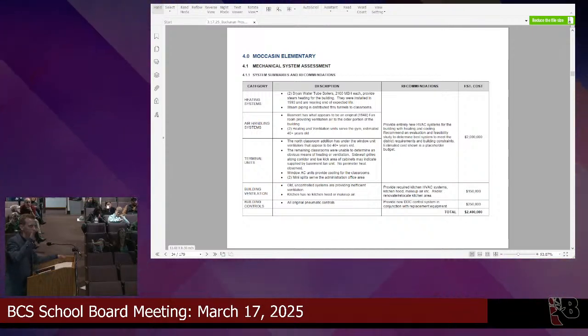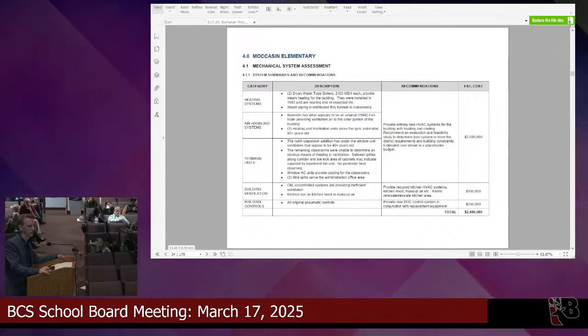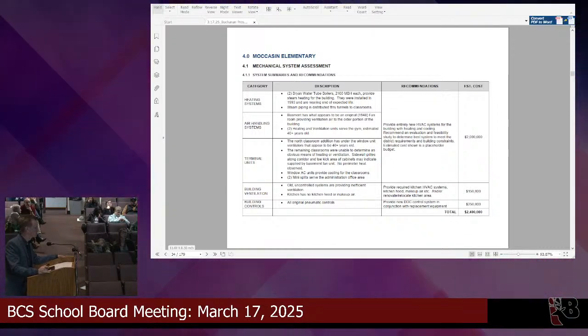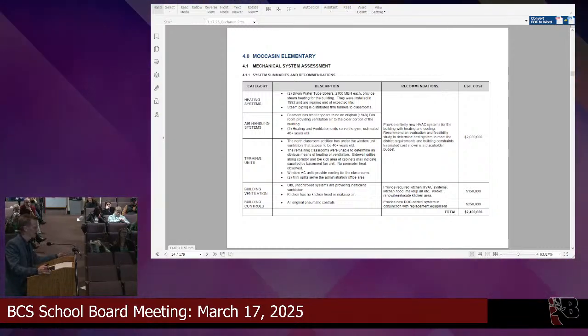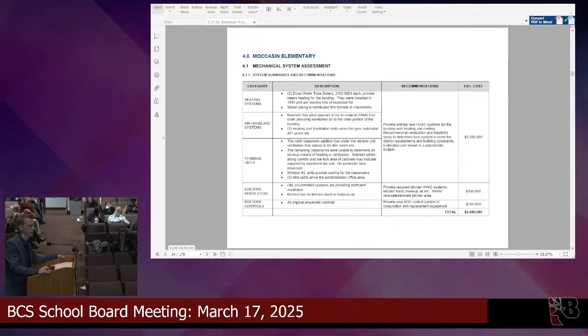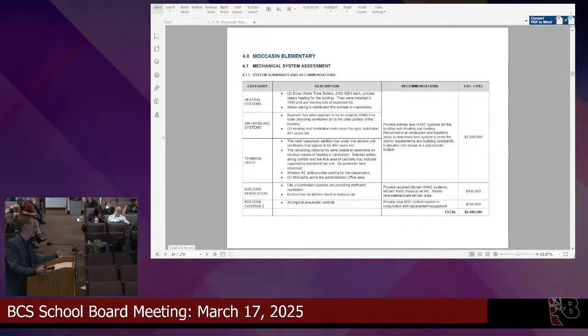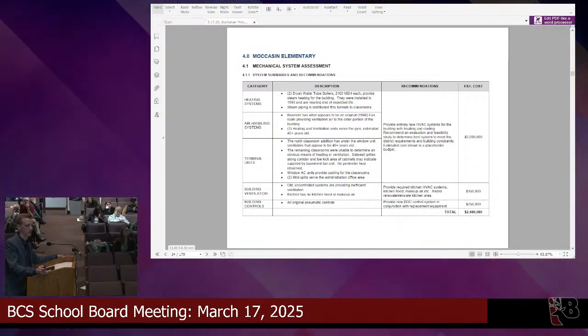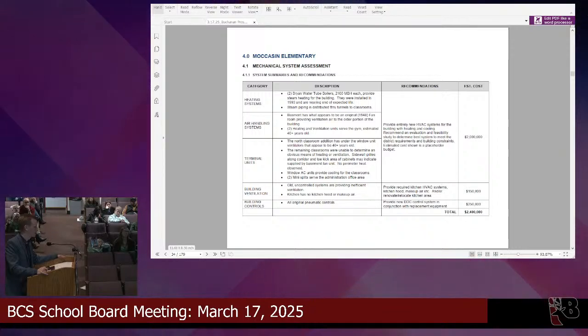We got a summary describing what the existing systems are for heating, air handlers, terminal units, ventilation. Another big item you'll see across the schools is controls. That's something staff has noted too, that there's a bit of a mishmash of control systems. This building has pneumatic controls, and there's not a lot of availability to schedule equipment, maintain temperatures, or be efficient with its operation. So in this case, we're recommending it needs a new HVAC system for the building. That's just the general recommendation. We've got costs, and what that system looks like really requires a little bit of study, feasibility, and analysis, since there's multiple ways you could do it for heating and cooling.